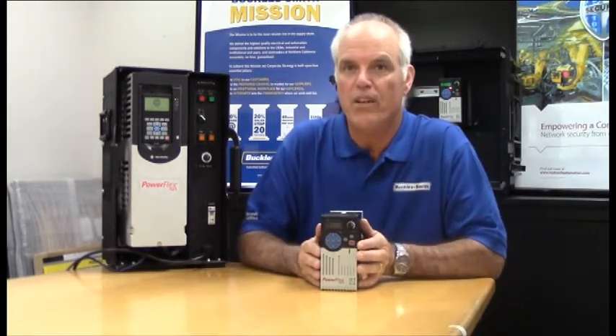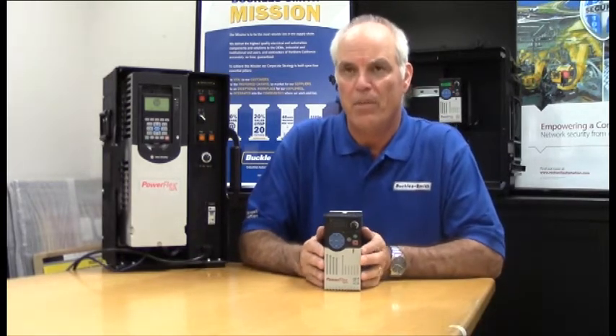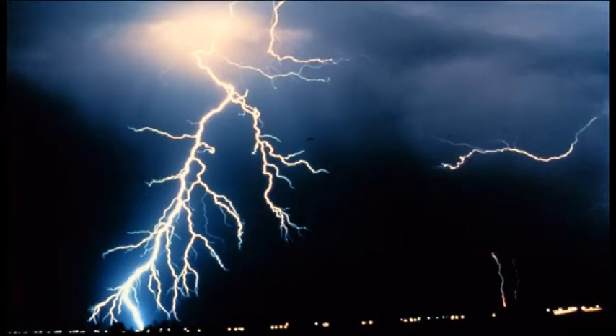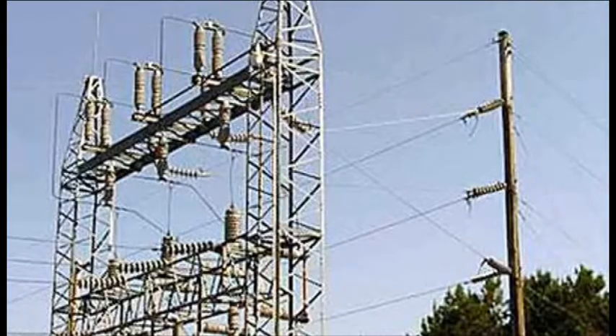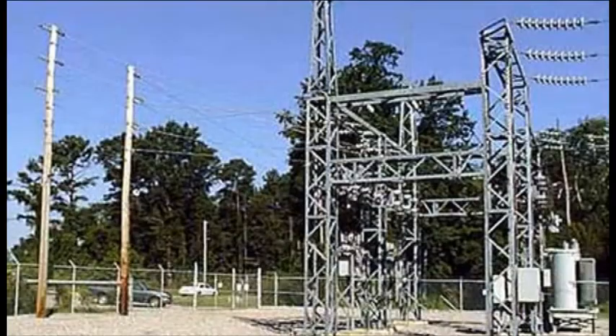Today's Rockwell drives have a failure rate of less than 0.5%. Of those failures, the vast majority are environmental in nature, usually related to heat. But the next most common failure mode involves electrical disturbances of the power grid. Spikes and sags in utility power are all too common as we get our electricity from an aging grid that's not designed to handle today's demand.